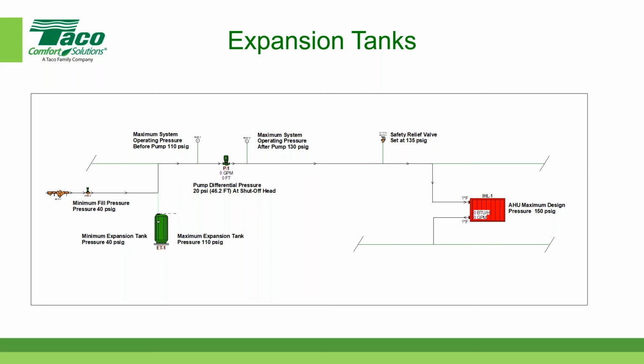Now, that may not be practical, especially in terms of the height of the building. So another way of getting around that is that if you design a piping system that has, say, a single return from the highest point of the building down to the bottom of the building, and that return piping is sized so that the pressure drop at full design flow is negligible, then the return pipe acts like a dedicated pipe to the suction side of the pump. Now, that requires a substantial amount of design modification and calculations. So the simplest thing to do is to run a dedicated line. But yes, you can put the tank at the top and the mechanical room at the bottom.